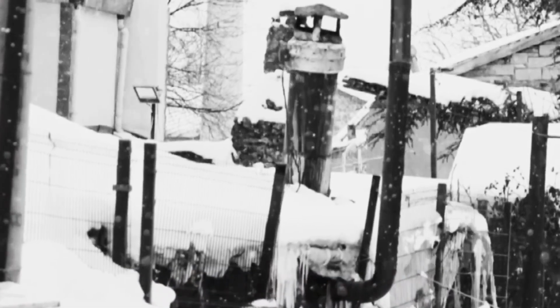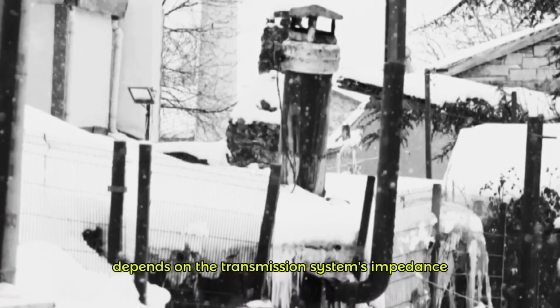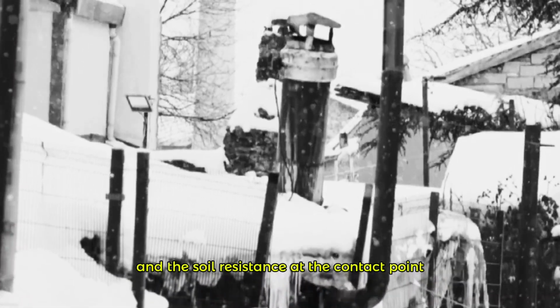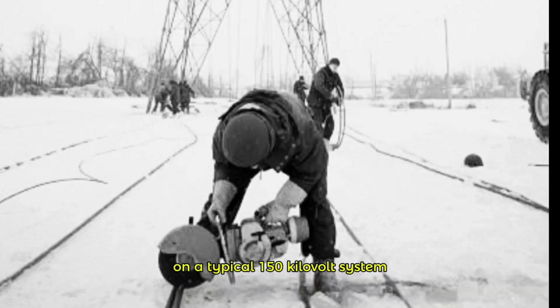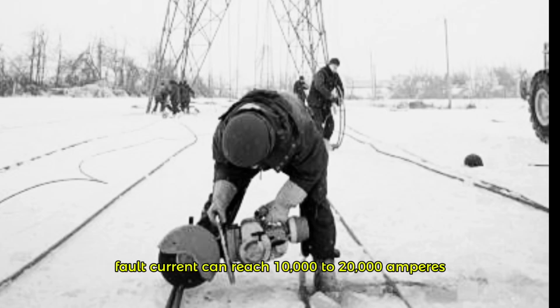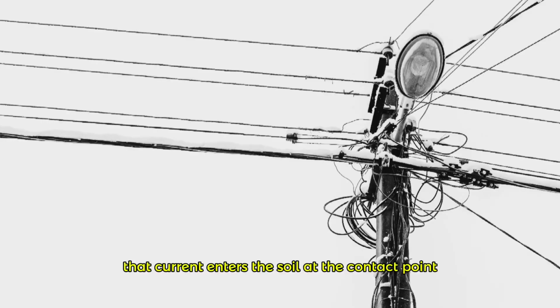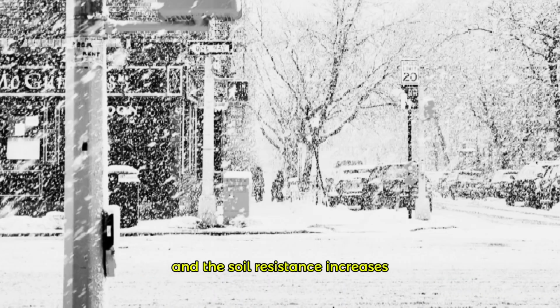When a 150 kilovolt conductor contacts Earth, the fault current that flows depends on the transmission system's impedance and the soil resistance at the contact point. On a typical 150 kilovolt system with substations within 50 miles, fault current can reach 10,000 to 20,000 amperes. That current enters the soil at the contact point and radiates outward in all directions. The voltage at the contact point rises sharply, briefly near the full system voltage, and drops as the current spreads and the soil resistance increases with distance from the fault.